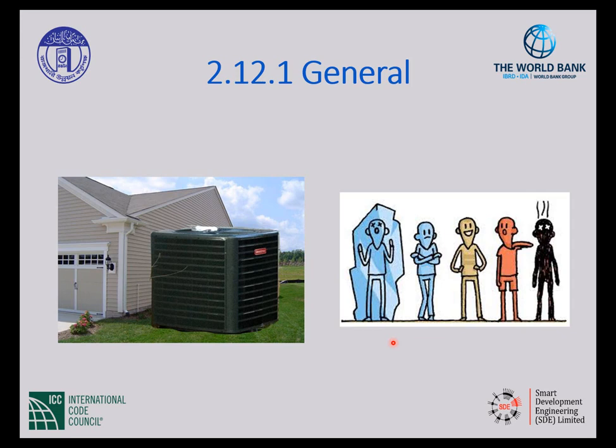What this is telling us is that I'm not going to just do anything. I'm not going to freeze people out or overheat people just to save energy. I have to keep comfort and environmental requirements. They can't be sacrificed just at the cost of energy efficiency, right? Oh, I'm just not going to heat the building at all. That way I save a lot of energy. No. And then it says, for those special applications, the hospitals, labs, and things like that, there are times when energy efficiency is on the bottom of the totem pole when we're talking about what the requirements are for some of those places. The design concepts and the parameters, they have to look at the minimum energy levels because there might be other things that overrule that.